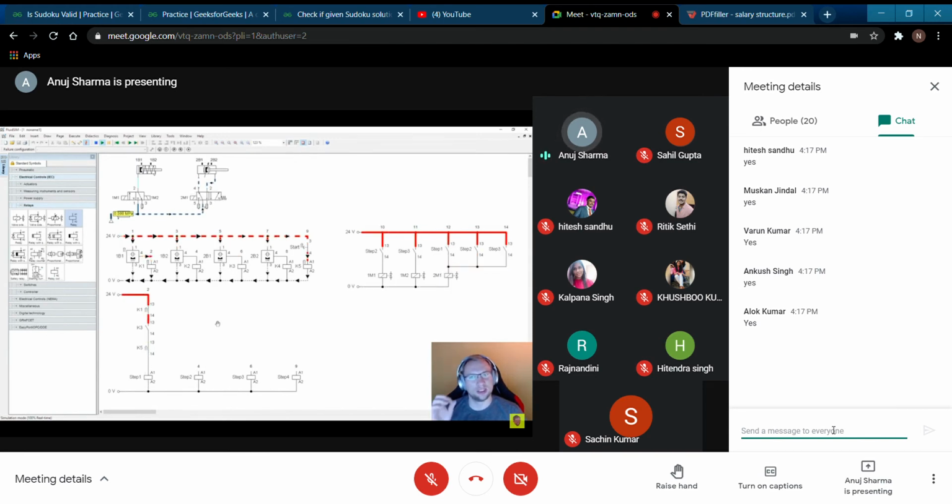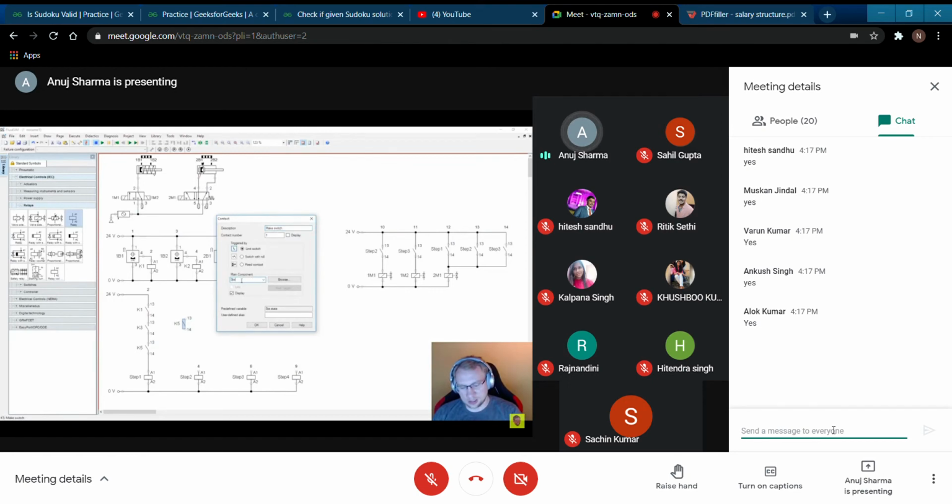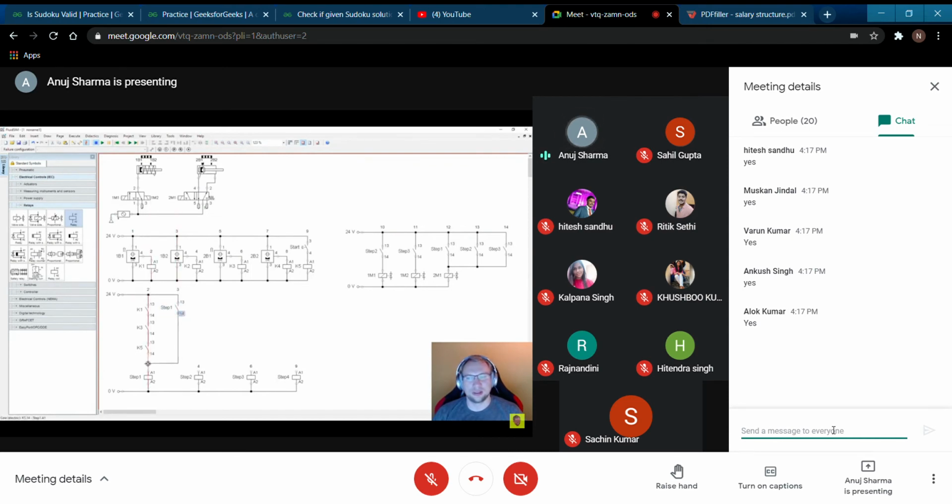What we want is this one should latch itself, right? It should activate, the step should activate, and it should stay in that step. And that's why for every step, we will also ask, is the step active at that time? Is step 1 active, then please stay activated, and this will prevent us from doing that over and over again. Right now we're in step 1 and we stay in step 1. That's very good. The problem right now is how do we get out of step 1?